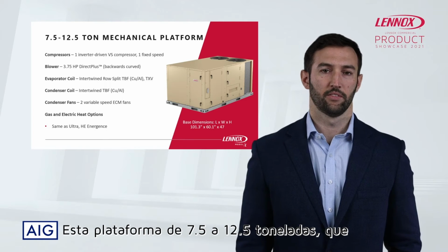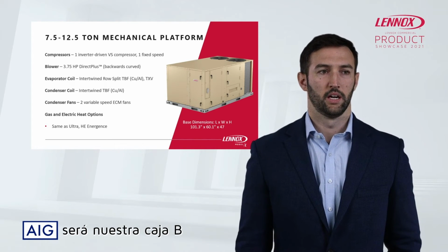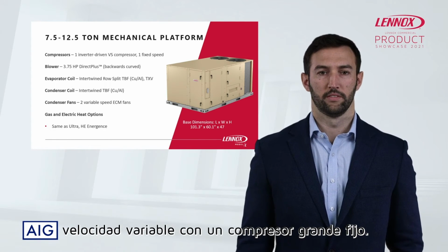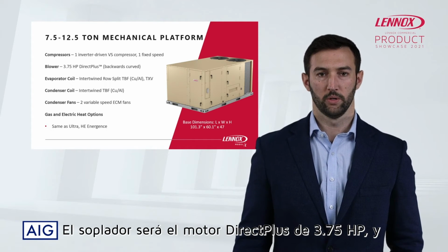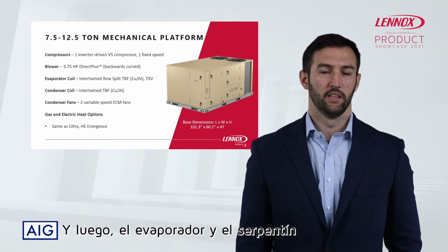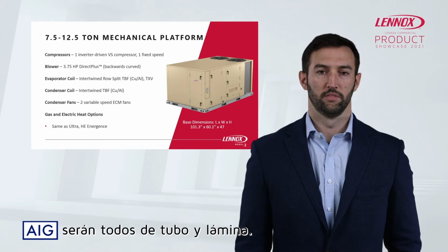Looking at the 7.5 through 12.5 ton platform, this is going to be our B-box. So we're going to have a lead variable speed compressor with one fixed speed lag compressor. The blower is going to be the 3.75 horsepower Direct Plus motor, and that's going to be for all of the tonnages in that range. And then the evaporator and condenser coil, like the A-box units, will be all tube and fin coils.